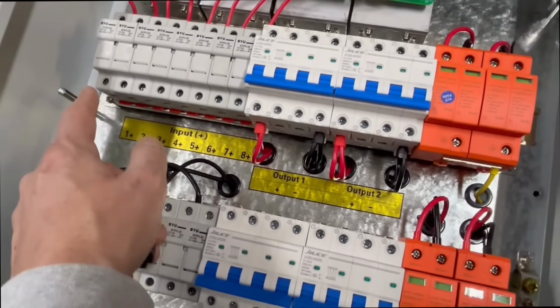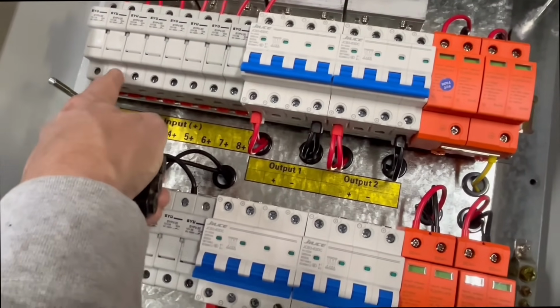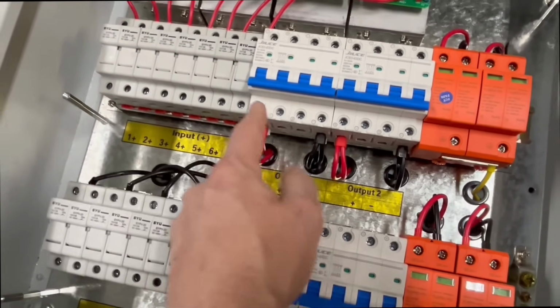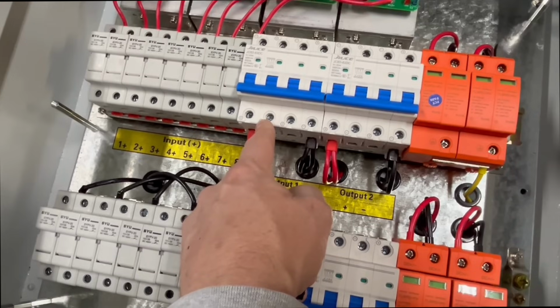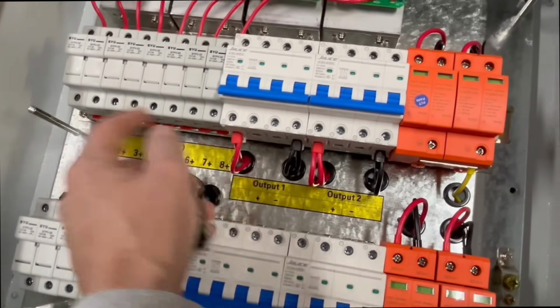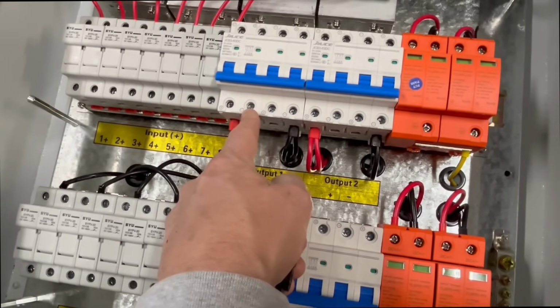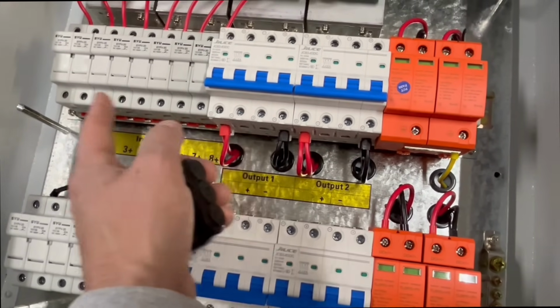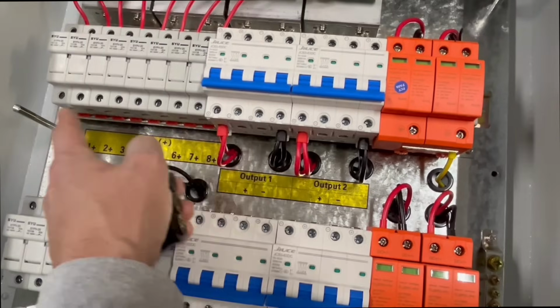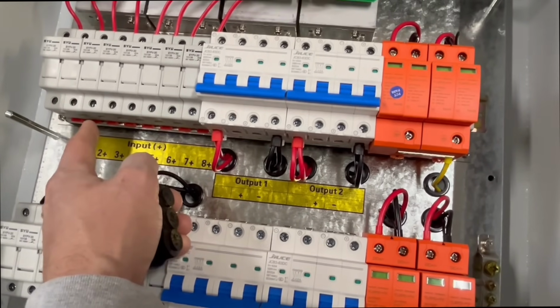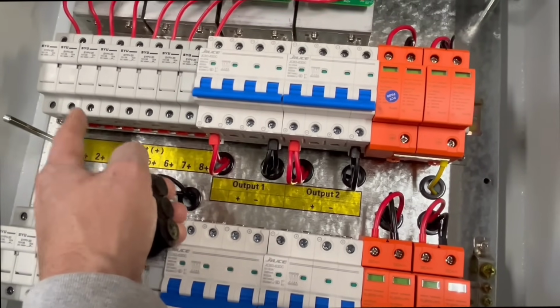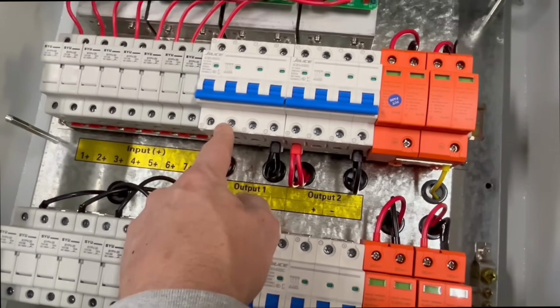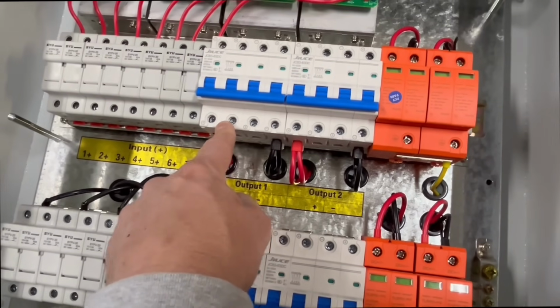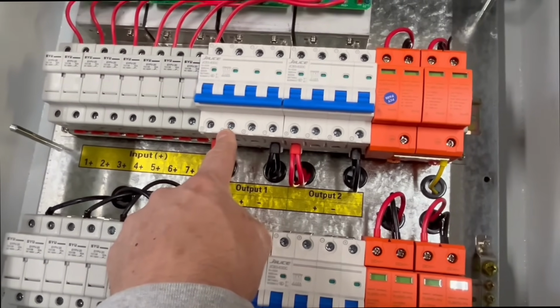So if you're leading one positive in here, another positive in here, the positive coming out here is going to be double the amperage. So let's say your array has 10 amps. Coming out of here, it's going to be a 20 amp string, the same voltage as you put in it. So if it's 350 volts and 350 volts and 10 amps, it's going to be a 350 volt string coming out at 20 amps. I hope that makes sense.